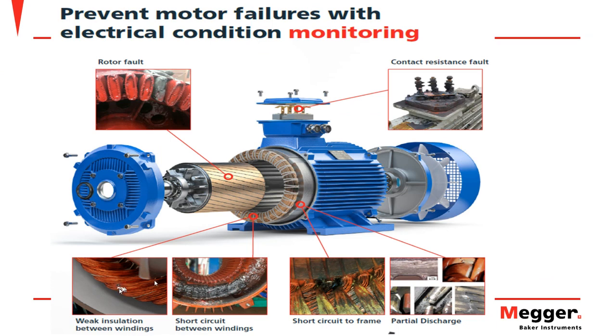So we'll monitor it. It might be 1400 volts next time, then it might drop down to 900. But as soon as it gets to the supply voltage at, say, 400 volts, then we know that we've got a potential dead short, and that's when it starts to burn out. So this is where our window of opportunity kicks in, and we can start to plan our predictive maintenance.